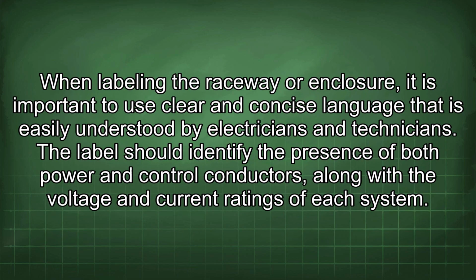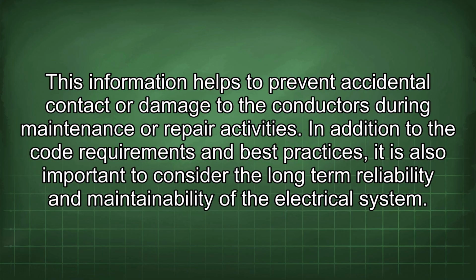When labeling the raceway or enclosure, it is important to use clear and concise language that is easily understood by electricians and technicians. The label should identify the presence of both power and control conductors, along with the voltage and current ratings of each system. This information helps to prevent accidental contact or damage to the conductors during maintenance or repair activities.